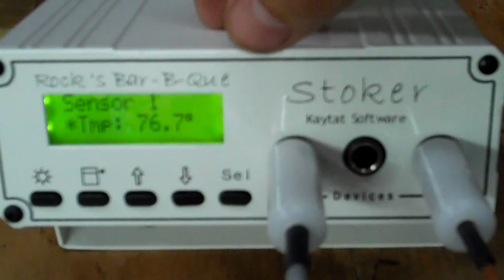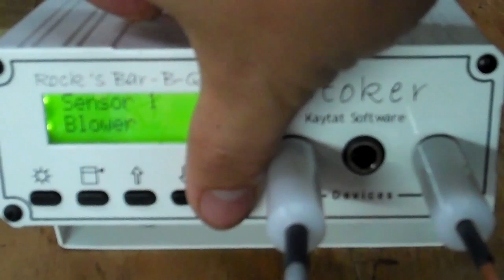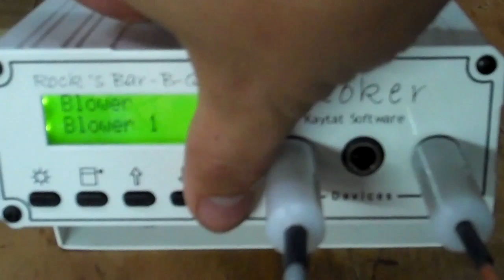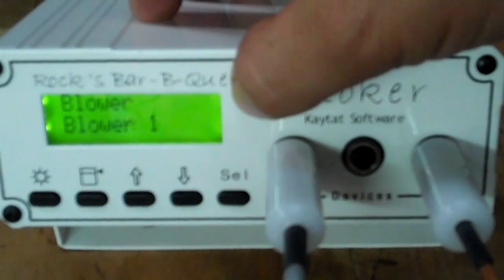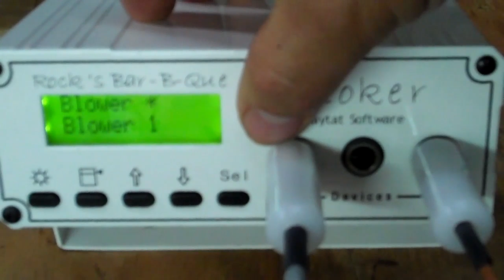All the blowers will be named in sequence, blower 1, blower 2, depending on how many blowers come with your system. So to assign the blower to the sensor, go ahead and press select at the sensor, and then select again to enter the sensor menu. Now it says sensor 1 blower, which is where we'll assign the blower. You press select. If it's assigned, there will be an asterisk here. Since there's no asterisk, the blower is not assigned to the sensor. Press select to assign it. It'll say please wait, and then it'll go back to the menu. Now the asterisk has appeared, so if the temperature of the probe was set at a target that's above the ambient temperature in the shop, the blower would come on.